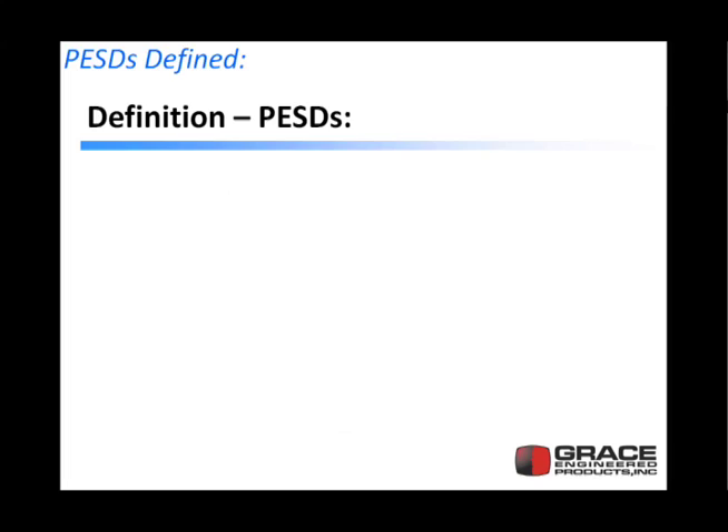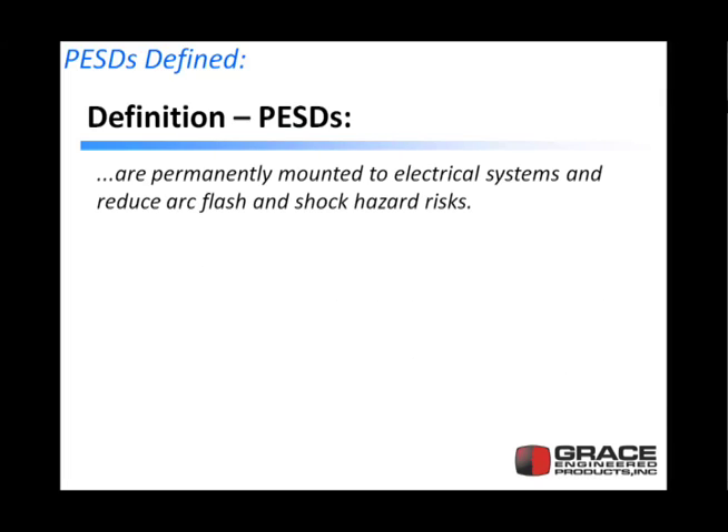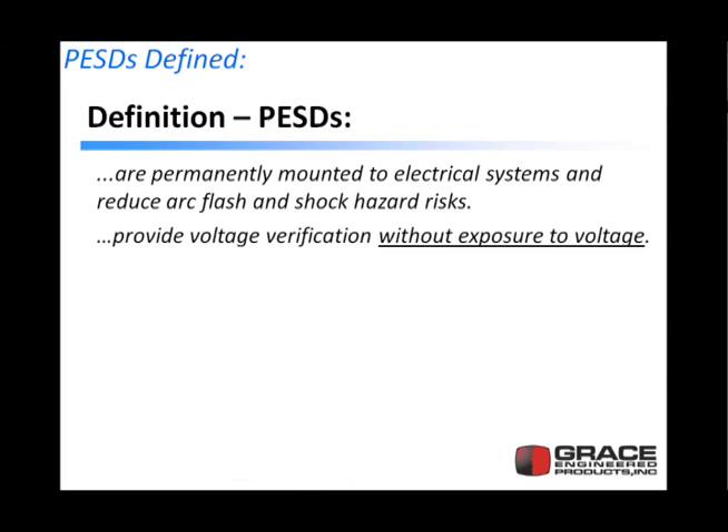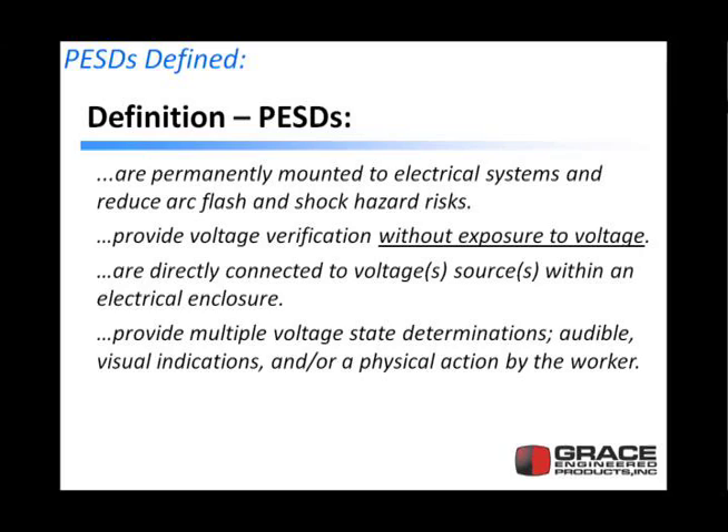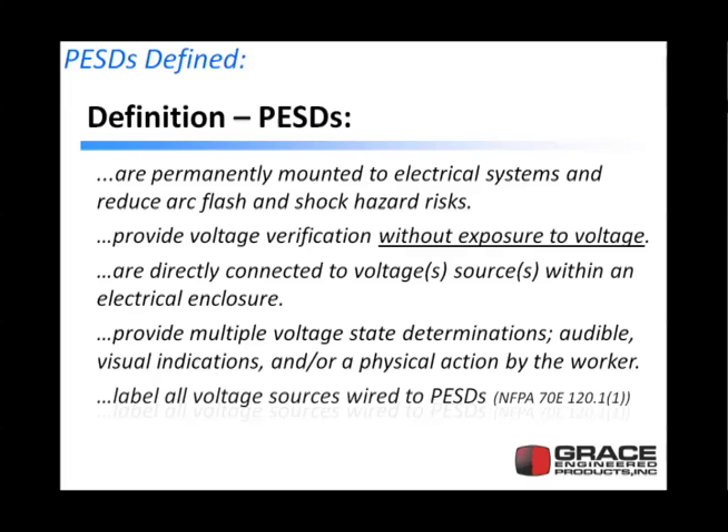Let's first define a permanent electrical safety device. They are permanently mounted to electrical systems and they reduce the arc flash and shock hazard risks. If they're not going to reduce risks, there's no sense in putting them on your panel. They provide voltage verification without exposure to that voltage, so they keep your people away from live voltage. They are directly connected to the voltage sources within an electrical enclosure. They provide multiple voltage state determinations, audio-visual indications, and require physical action by the worker, so they involve the worker in the process. And they label all voltage sources wired to permanent electrical safety devices.